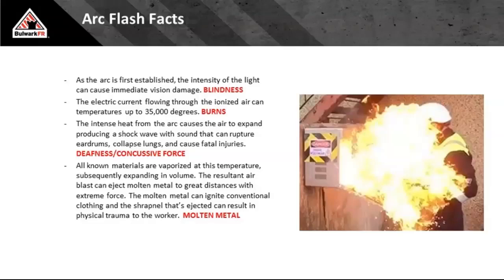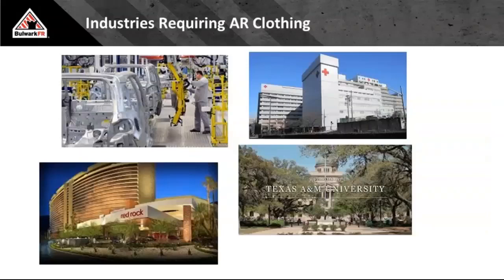Then you get concussive force. About 2,200 square foot pounds of concussive force is driving out at you. We see cracked ribs, punctured lungs, and other kinds of injuries occurring from that. And then also, if you're in a confined space, if you're in an electrical room and there's a cinder block wall behind you, and along with that concussive force you're trying to get away, you're now thrown in against solid objects. So we see secondary type injuries occurring in these types of incidents. So we've got a lot of bad stuff going on. Where does this bad stuff potentially happen?